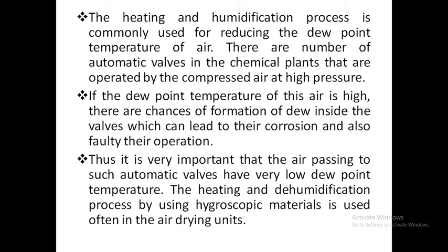If the dew point temperature of this air is high, what will happen here? There are chances of formation of dew inside the valve, which can lead to corrosion and faulty operation. This is malfunction. It is very important that air passing to such automatic valves has a very low dew point temperature. So the use of the heating and dehumidification process is reducing the dew point temperature of air.